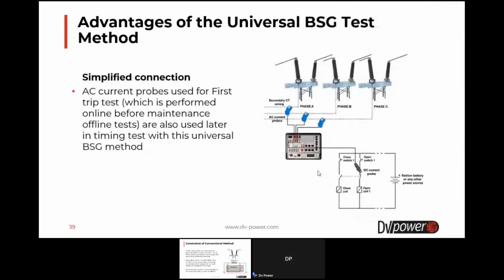That is shown in this figure. So this is the diagram when the first trip method is applied. If you want to record the timing when the circuit breaker is under voltage, and when you want to perform an online test, you can connect to the main circuit, but you need to use the AC probes to record changes of the secondary current transformer, which is used to detect the instant of the arcing contact separation or touch. So after the first trip test is performed, these same AC probes are later used for this universal timing test method. You need only to disconnect the circuit breaker from its circuit and network and connect the current cables. But you have also connected these AC probes.